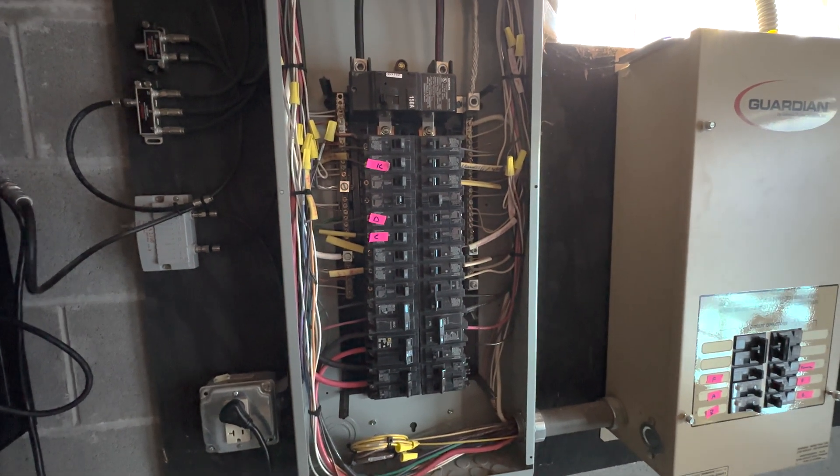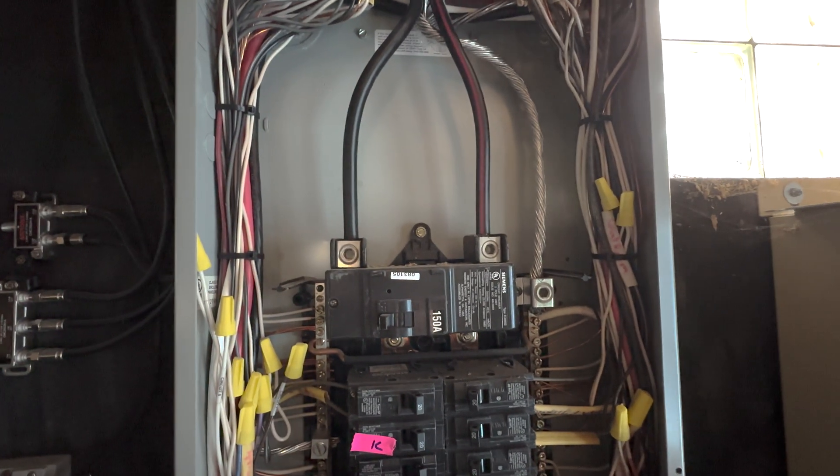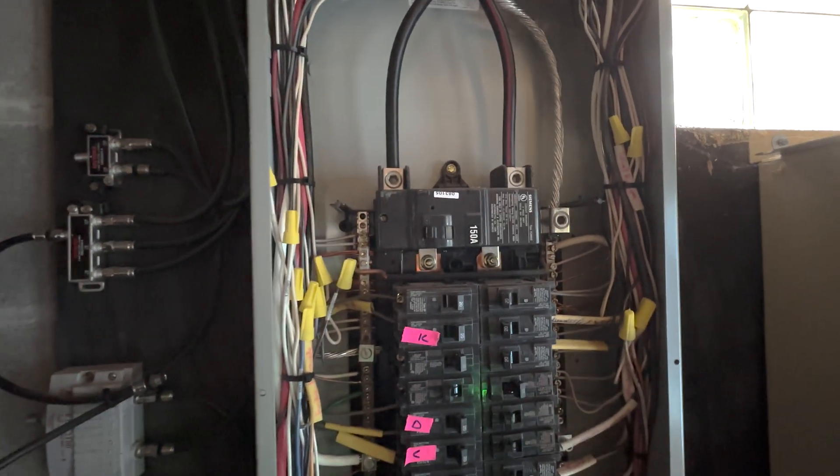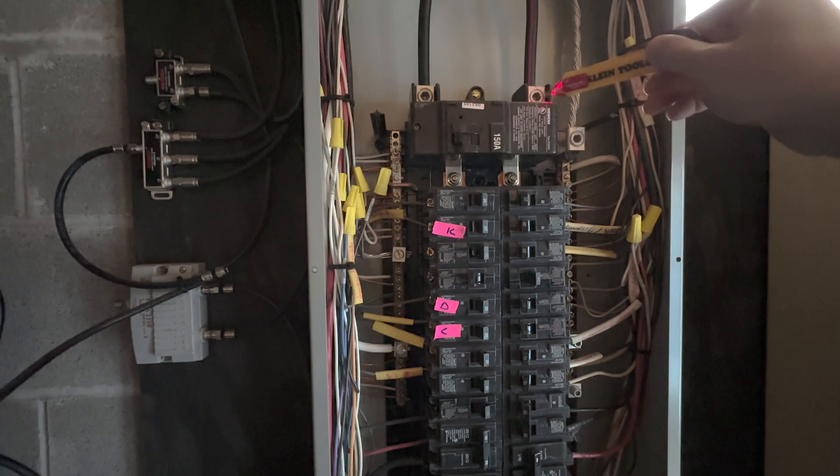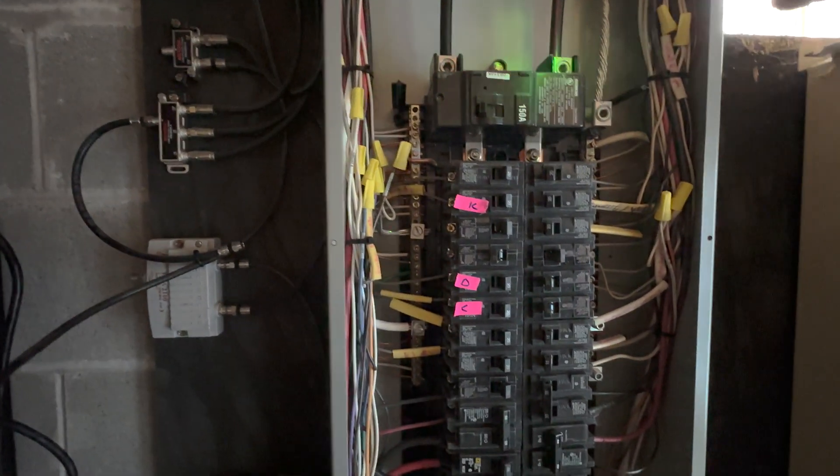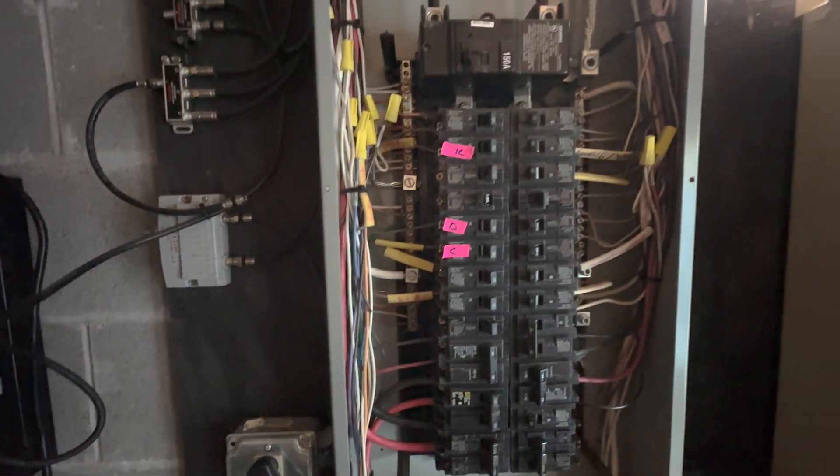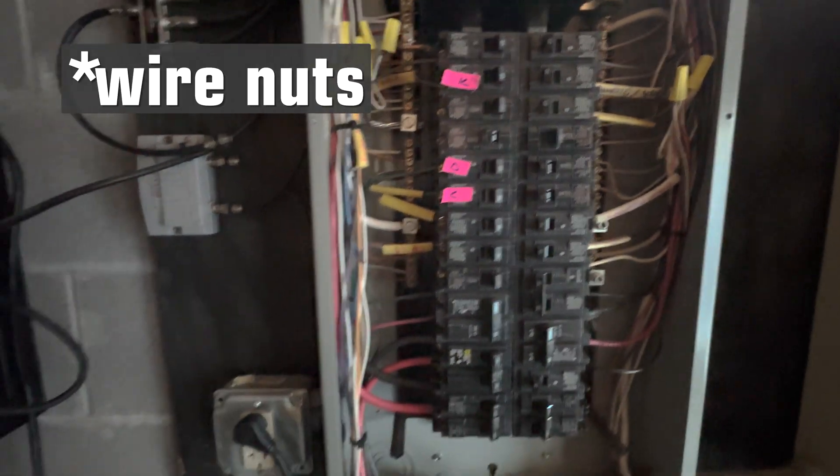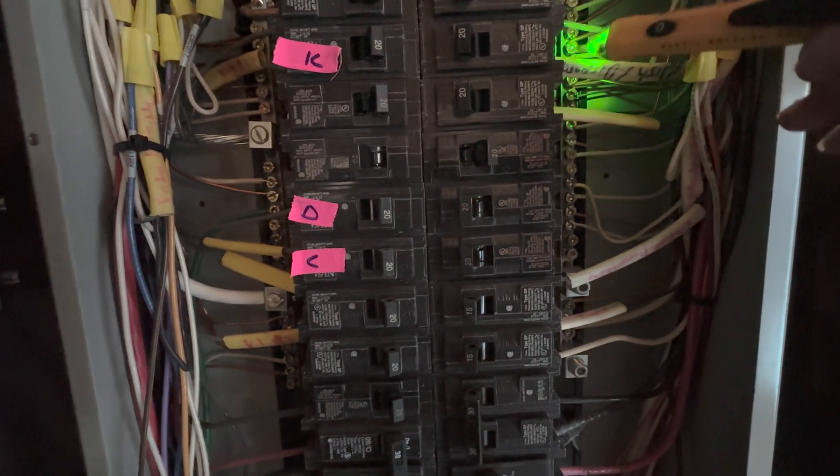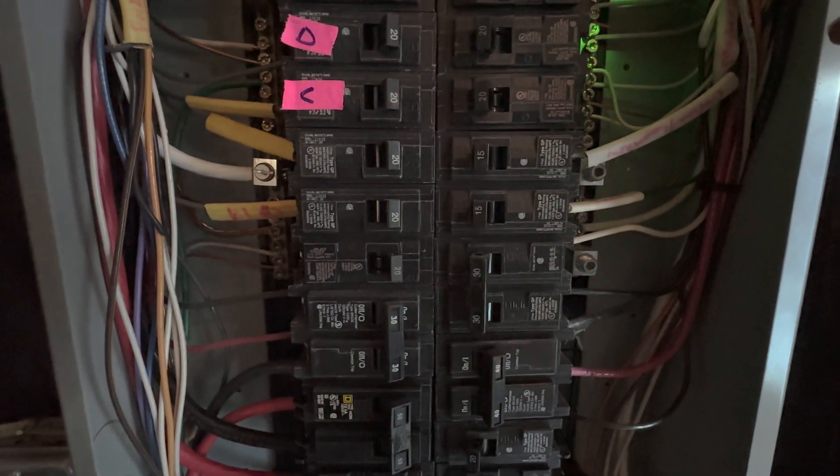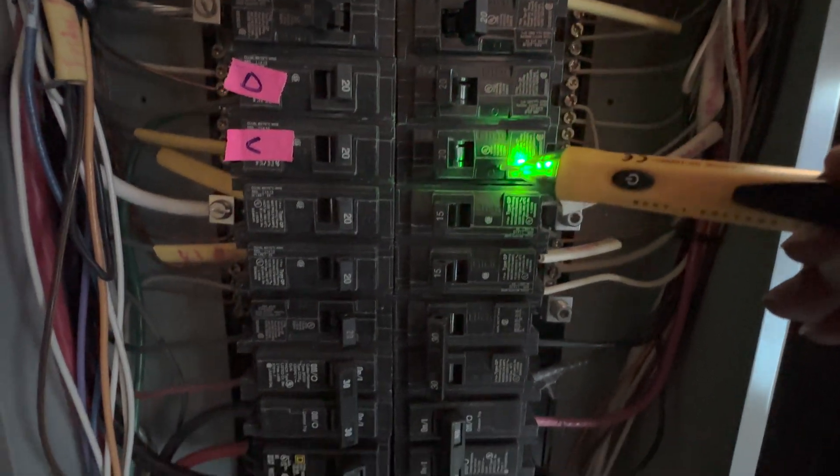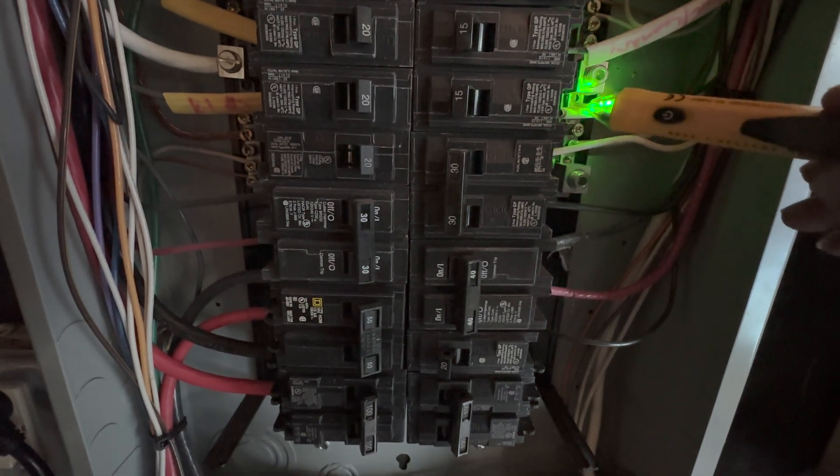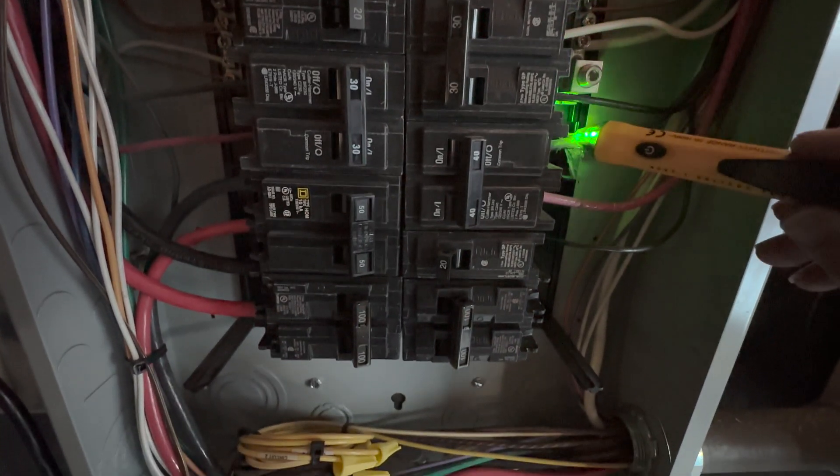All righty. So, in our panel, these are our main lugs up here. And this is an old enough panel that it doesn't have the little safety guards on them. So, I have my little voltage tester. That's still hot. That's still hot. So, the interesting thing about the whole house generator is a lot of this stuff is just split with wire ties. So, as far as our bus bar goes, let's see what we've got. What's hot on this side. What's hot on this side? So, there's a lot of breakers that are unused. So, I've got one, two, three breakers that are unused.